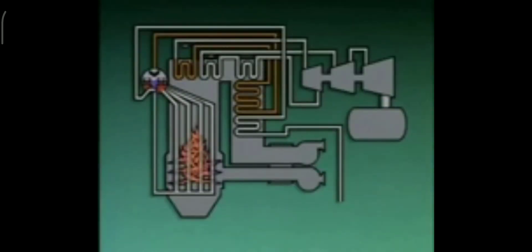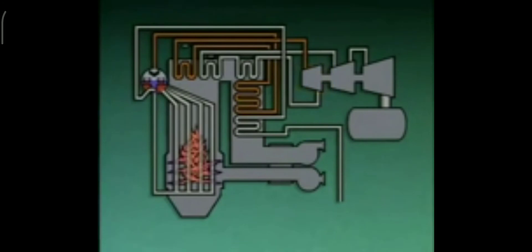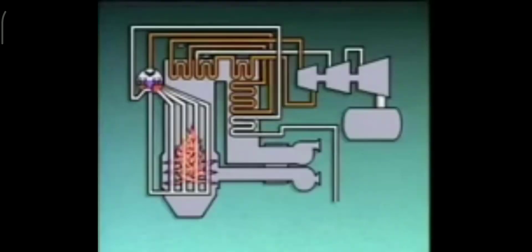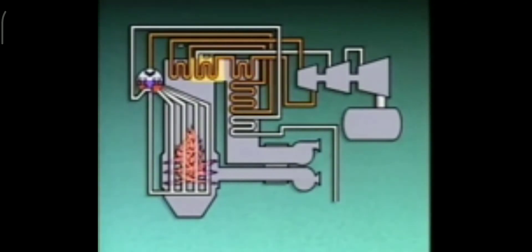From the secondary superheater, the steam goes to the high pressure, or HP, section of the turbine. As the steam flows through the HP section, it gives up a lot of its energy and its temperature and pressure drop. Before it moves on to the other sections of the turbine, the steam returns to the boiler, where its temperature is increased as it flows through one or more reheaters. Reheaters are very similar to superheaters — they use heat from the boiler furnace or from hot combustion gases to raise the temperature of the steam. This boiler has a primary reheater that the steam enters first as it comes from the high pressure section of the turbine. After the steam flows through the primary reheater, it moves on to a secondary reheater.